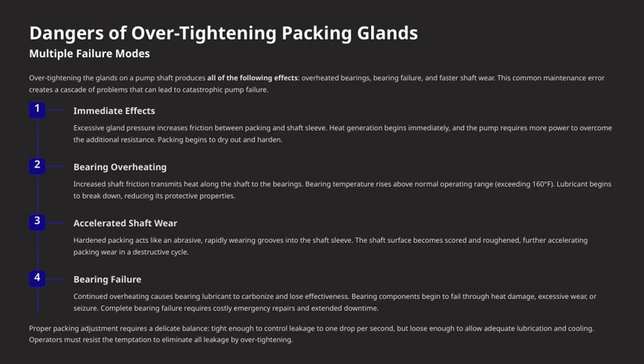Now, what happens immediately when you over-tighten? Excessive gland pressure increases friction between the packing and the shaft sleeve. This friction generates heat right away, meaning the pump has to work harder and consume more power just to overcome that resistance. Plus, the packing itself begins to dry out and harden, which only worsens the problem. As the heat builds up, it's transmitted along the shaft to the bearings. This causes the bearing temperature to exceed normal operating limits, often going beyond 160 degrees Fahrenheit. When this happens, the lubricant inside the bearings starts to break down, losing its protective qualities and making the bearings even more vulnerable.